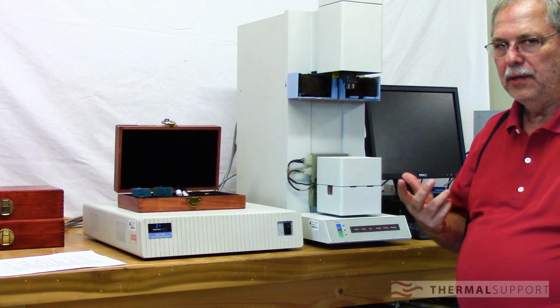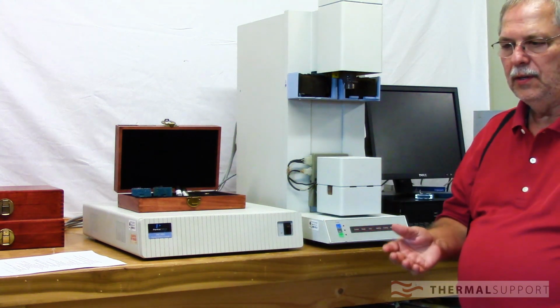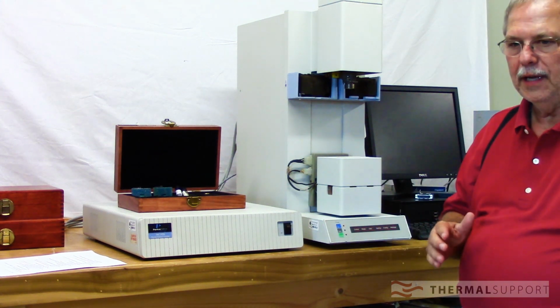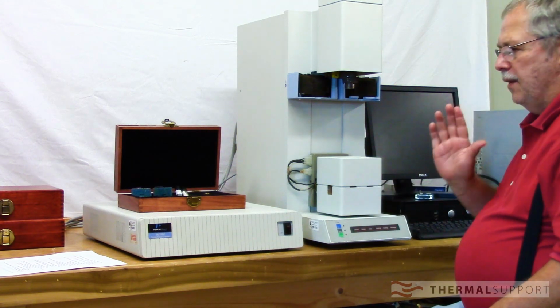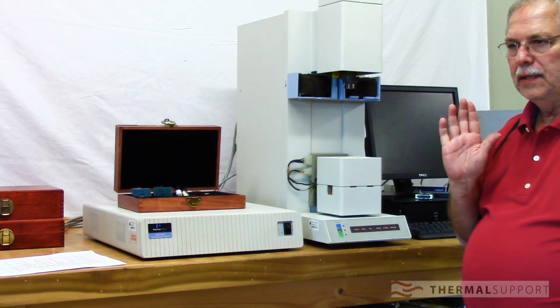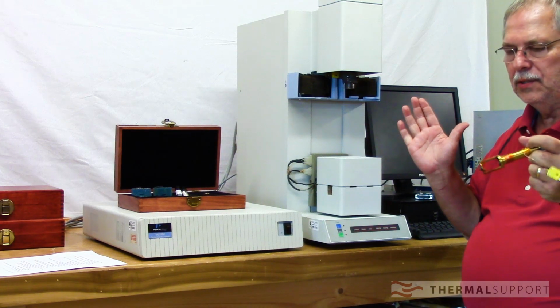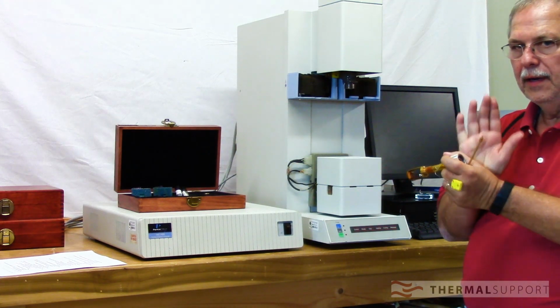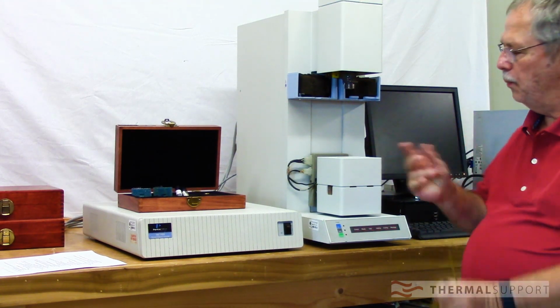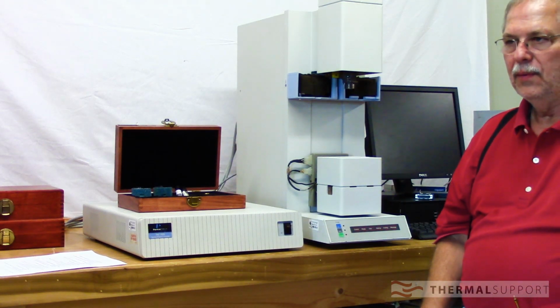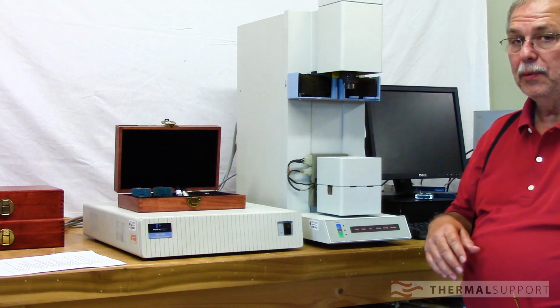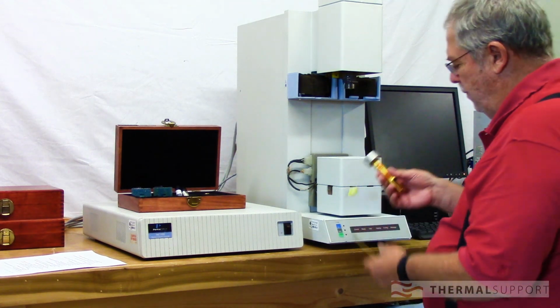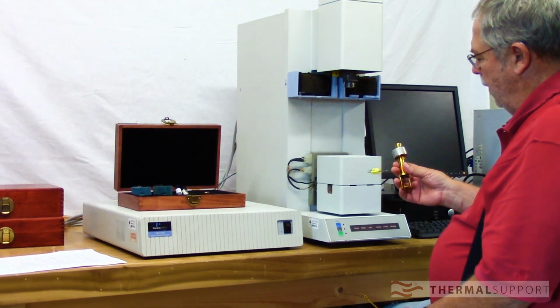Whichever measuring system you're using, once you do your indium and your zinc and you do your furnace calibration, everything will be referenced to that thermocouple on the side, and the calibration software will bring them together. You get a good solid calibration that way. If you're putting your thermocouple close to your sample, not so much. You really don't know where you're going to be, and it's hard to reproduce it. So we've gone ahead and put this together.